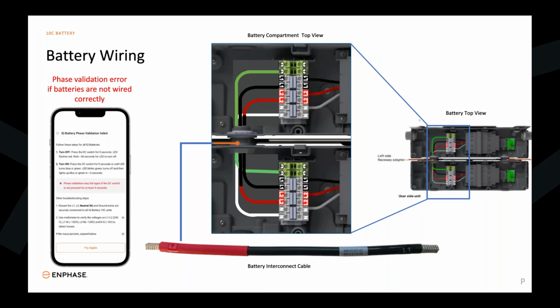We will have to wire in line 1, line 2, the neutral, and the ground. That's another important thing. With the previous generation products, we didn't have the neutral, but with the 10Cs, we do. So we want to make sure everybody's aware of that and doesn't make the mistake of not wiring in a neutral with these batteries. That's a great point, Jared, glad you brought that up. The neutral capability with this battery, and that extra conductor, make sure we're not forgetting that.